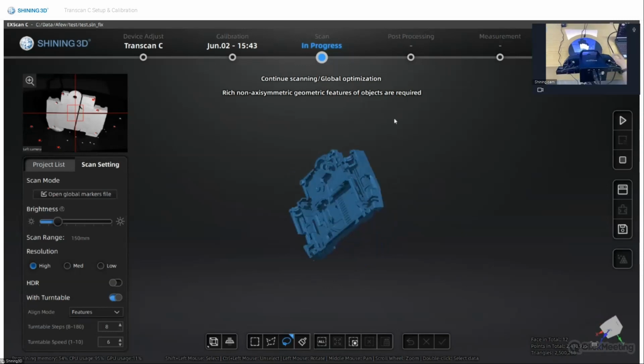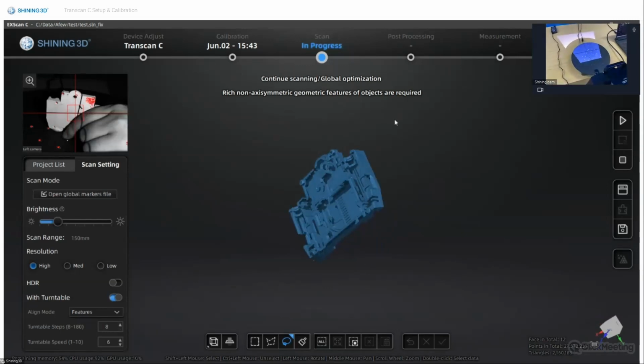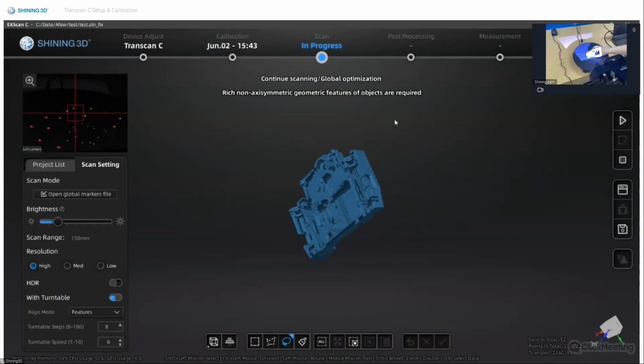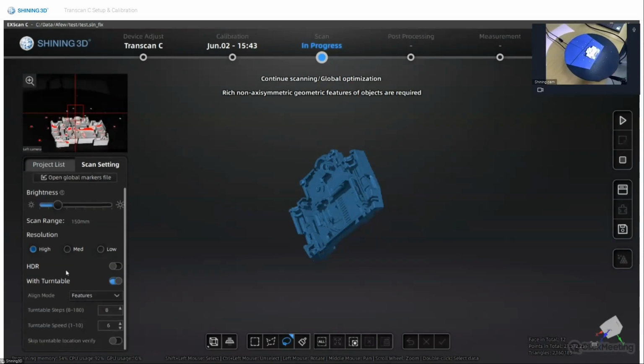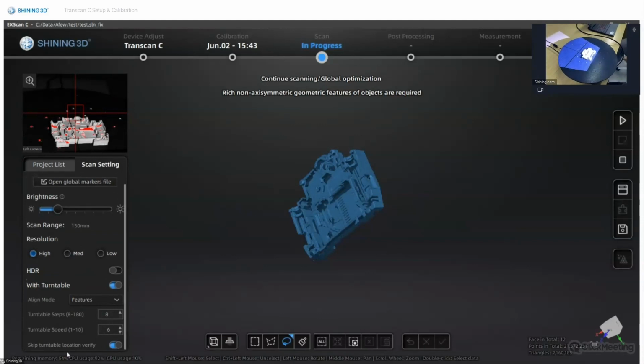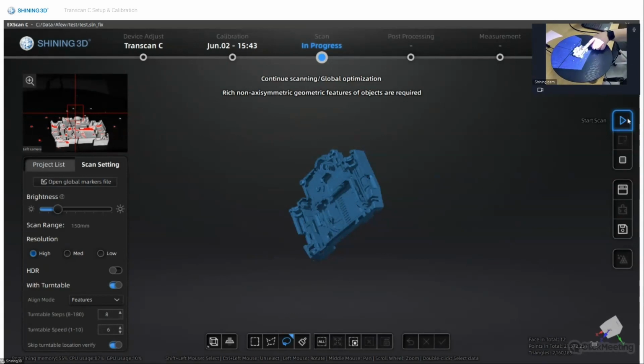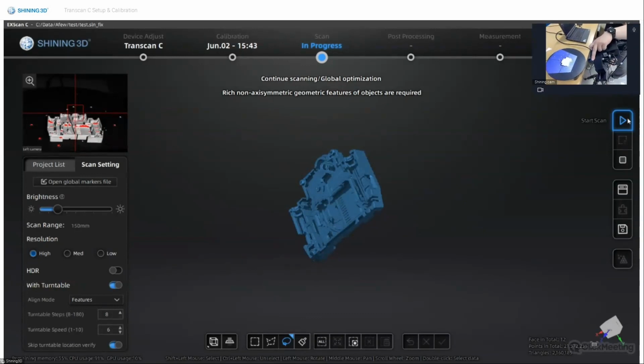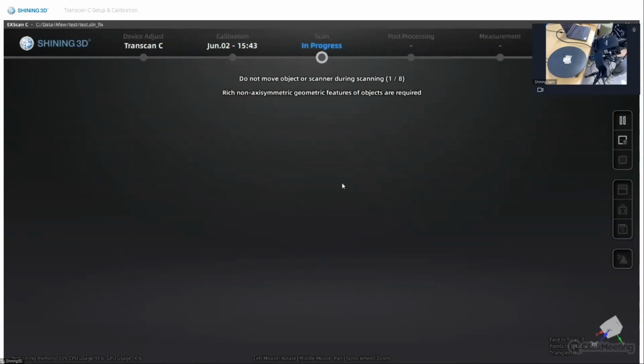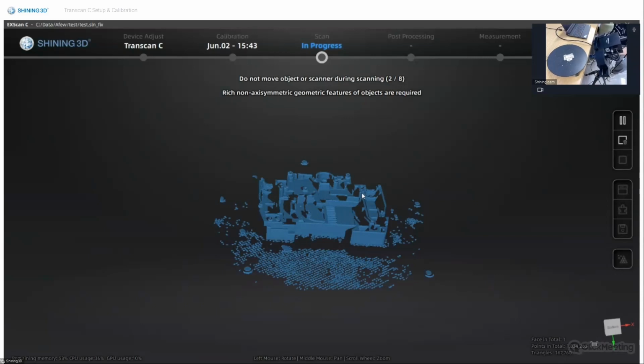Okay. So after the first run is done and the turntable location is verified, you can keep scanning by turning the skip turntable location verify on. And you see now it will not verify the data. And since the turntable position was not changed, it can align the data without problem.